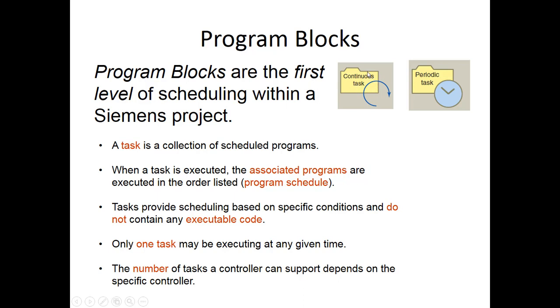Then there are periodic activities that the PLC does. What the periodic task does is interrupt the continuous task. The continuous is running and something periodic is called — it stops scanning your ladder logic to run the periodic task's logic. When that's done, it comes back to the continuous. Only one task is executed at a time. On our continuous tasks, they just scan in order — first one, second one, third one — with the lowest priority. You can set their priority by putting them in order.